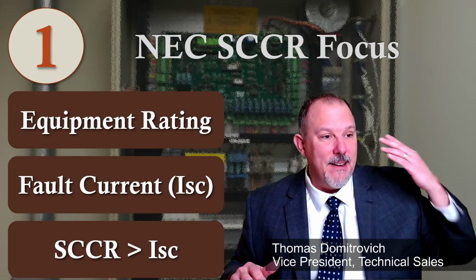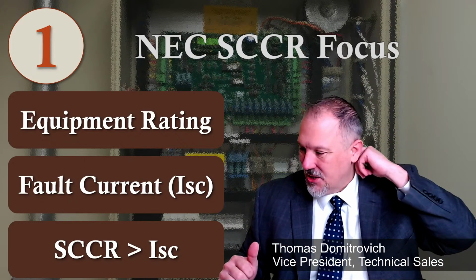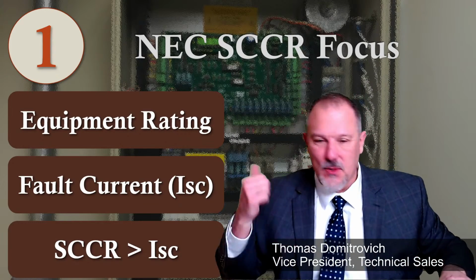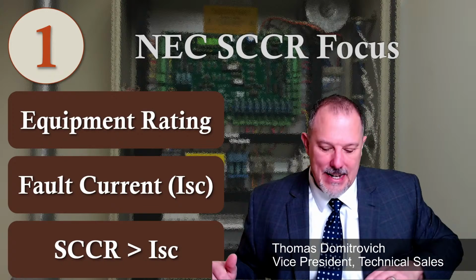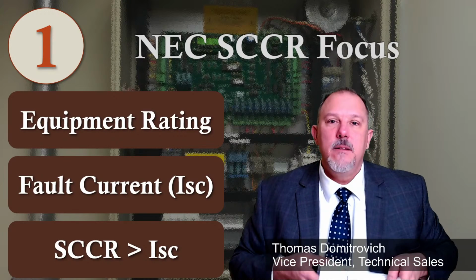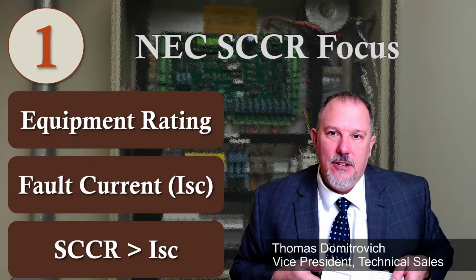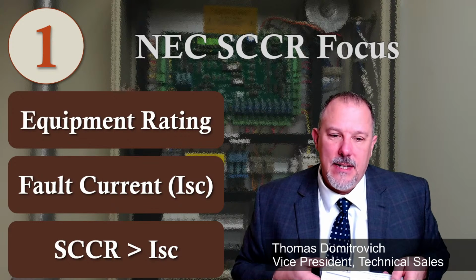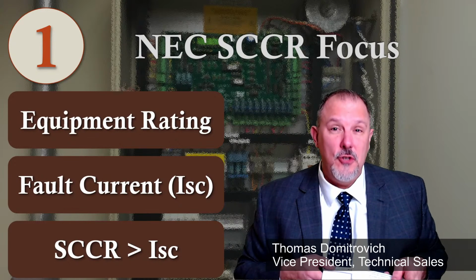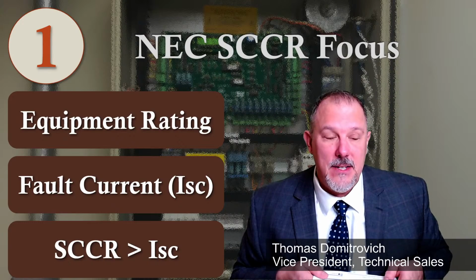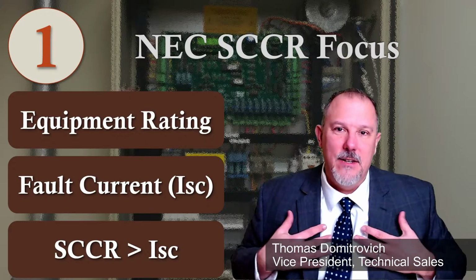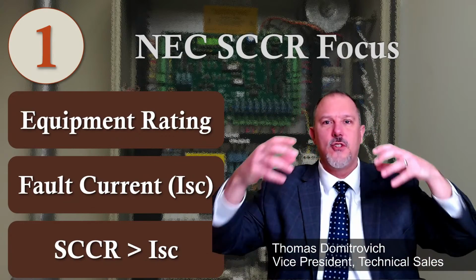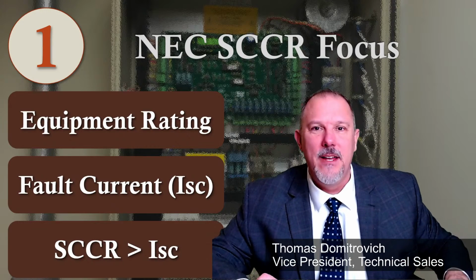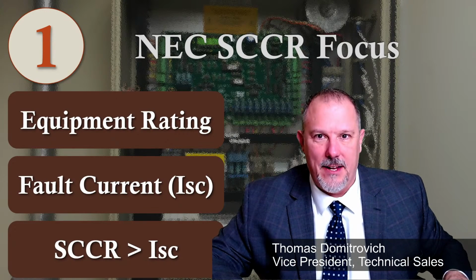I remember talking to a chief electrical inspector in New York City, a while ago, he's retired now. I asked him, what's the most fault current that you have in New York City at the bottom of these buildings? And he said 200,000 amps. And he says, do you know why we have 200,000 amps? And I was like, well, there's paralleling transformers and all this other good stuff. And he goes, no, Tom, because you don't make equipment greater than 200,000 amps.